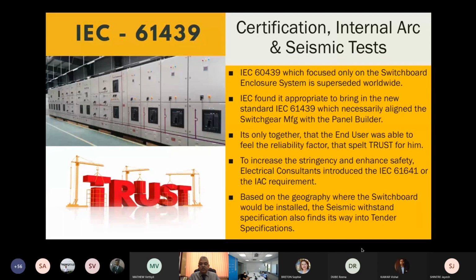So what is this IEC 61439 and internal arc and seismic test? So what is all this about? If we see, hardly a decade ago, what was prevalent was the IEC 60439 standard, which is also the IS 8623, if you look at the equivalent in the Indian standards. Now, whether it was IS 8623 or 60439, all it focused on was the enclosure and the bus bar system. That's it. So we could actually take an enclosure with the bus bar system to CPRI or ERDA, get it tested, and then we get the IEC 60439 certification.